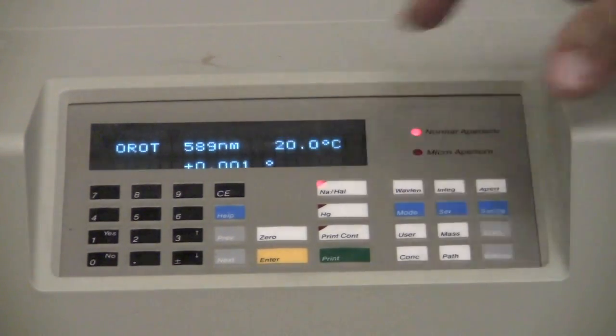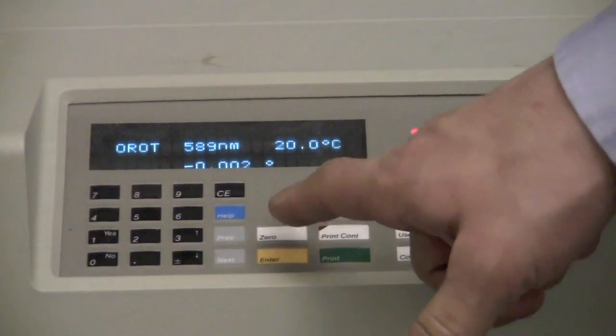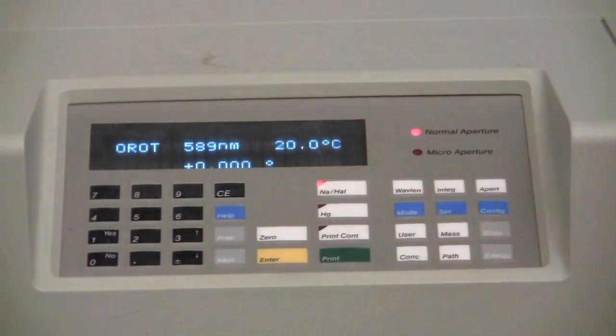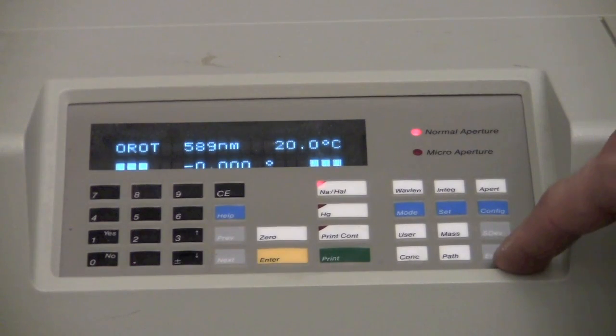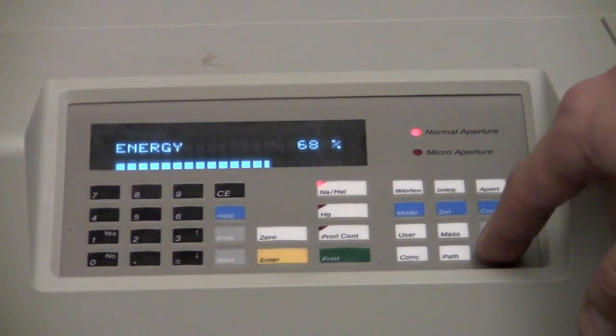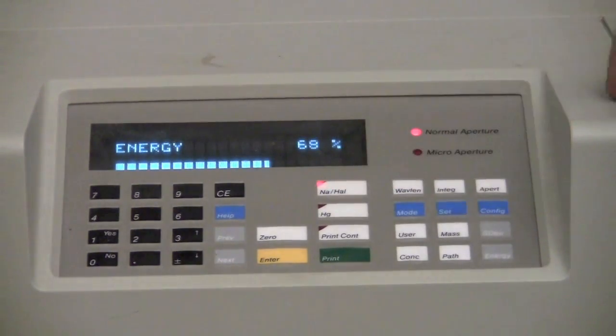If it's showing something slightly different than 0 degrees, you can re-zero it just by clicking on zero. One thing you can check is the energy. If you press the energy button, you can see the energy, and that's how much light is getting through the system. So more energy will give you a better signal because there'll be less noise.